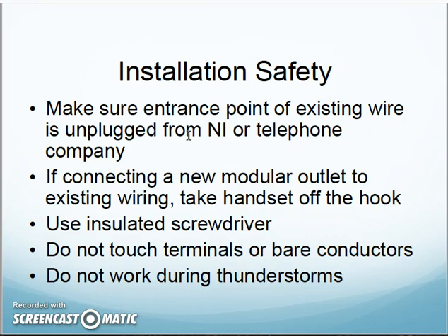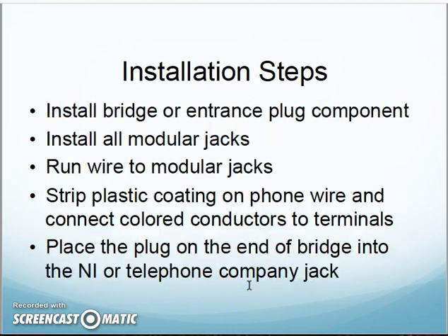So it's enough to give you a little bit of a jolt if you're holding onto those lines and a ring comes through. They talk about using insulated screwdrivers. Don't touch the bare contacts or terminals. Don't work during thunderstorms or surges coming in. Install the bridge or entrance plug component. That's the connection at the network interface box. I can plug or unplug that as I'm working on things.